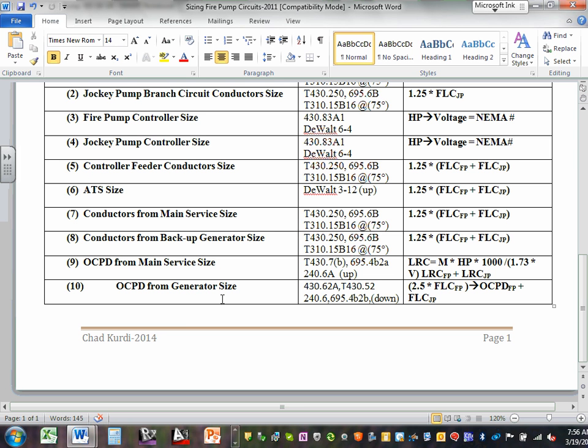For the overcurrent protection device from the generator side, you take 2.5, guys, and multiply it by the full load current of the fire pump. Then you take the overcurrent protection device of the fire pump and add it to the full load current of the jockey pump, and you size your overcurrent protection device down.